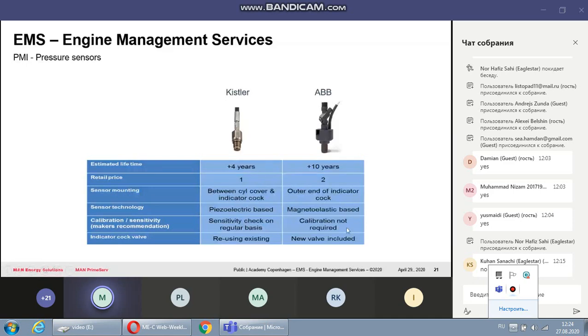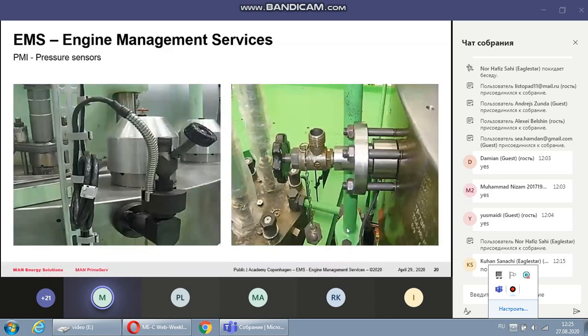However, if any of you are going on a tanker ship, I must tell you, a vetting inspector will ask you for the calibration certificate, and the certificate must be available on board. It is okay for 5 years. Otherwise, you must make your own kind of test report, which means you must use the portable transducer for calibrating them at least once in a year or once in 6 months, as the superintendent says. Then maintain the record, so then you will not get a finding. Otherwise, you might get a finding from the vetting inspector. Okay? Be careful.